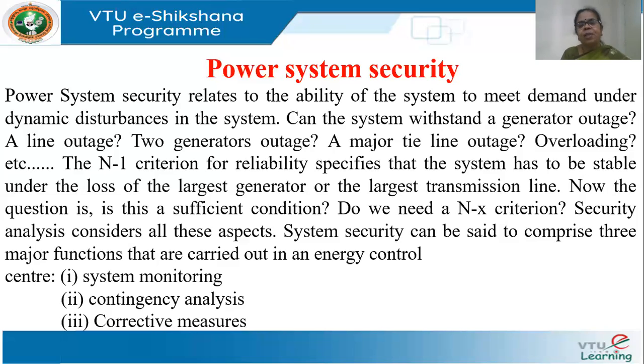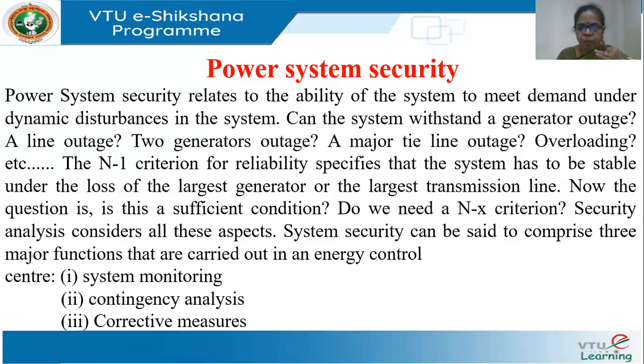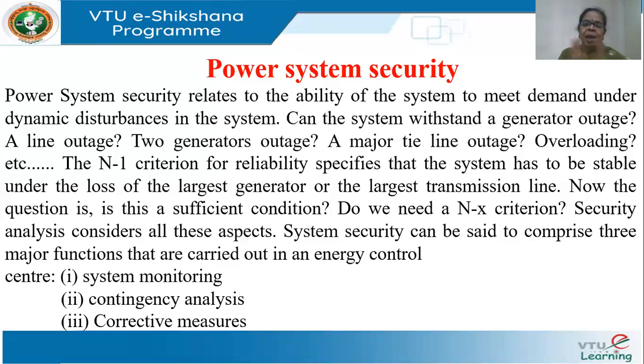The aim of all this is: first, the system should be stable with all load met. If that is not possible, the second best is to still operate the system with some load loss. If even that is not possible, go for a major load shedding, or go for what is called islanding — split your system into small islands each operating independently, with some heavy load loss. Finally, a very bad situation where you may end up in a blackout.